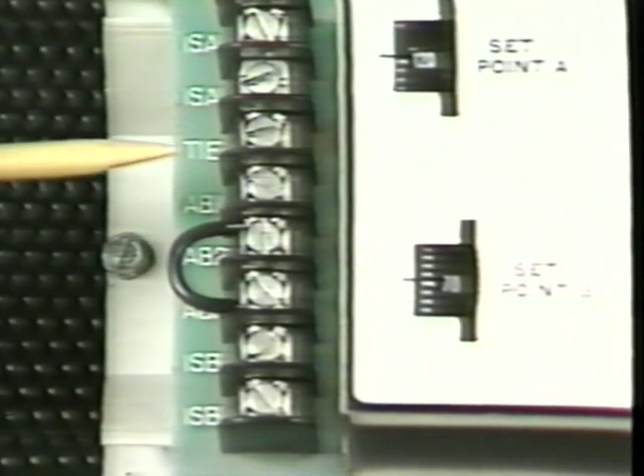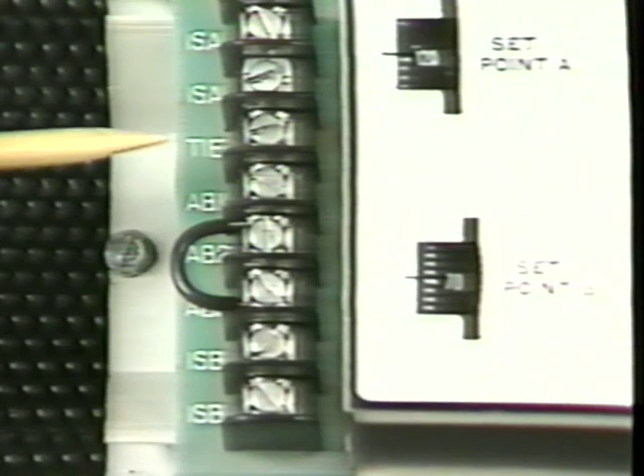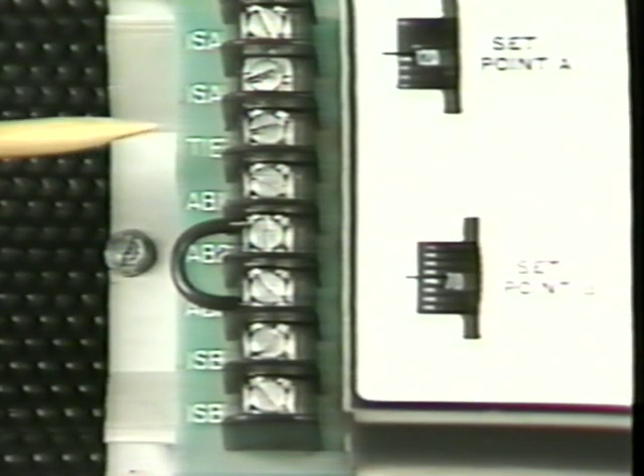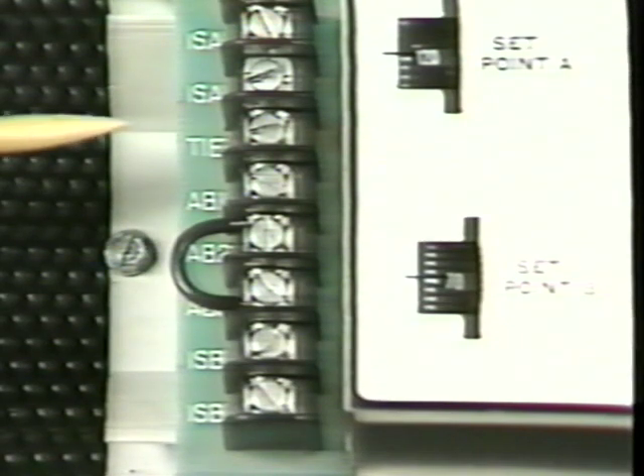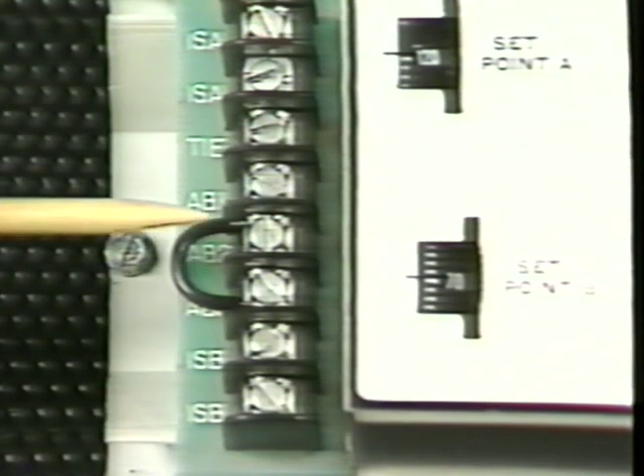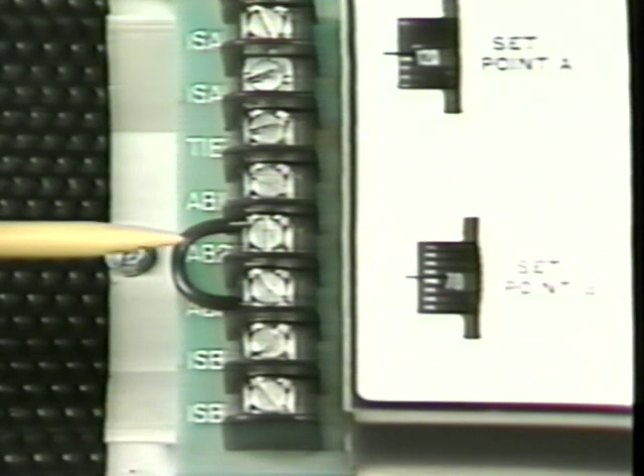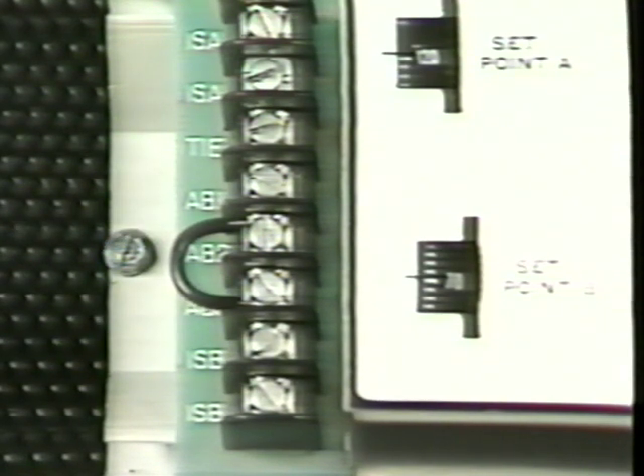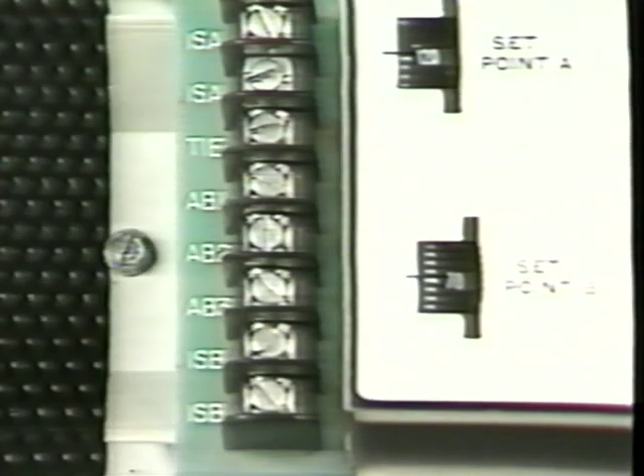AB1, auxiliary bridge input 1. This terminal permits the addition of remote set point adjusters or additional sensor signals through an external bridge module. It will accept a nominal 3.1 volt DC signal. AB2 and AB3, auxiliary bridge inputs 2 and 3. These terminals can also serve as signal inputs, but their primary function is easy disable of Bridge B when no reset is required. Removal of the factory installed jumper disables the Bridge B output.